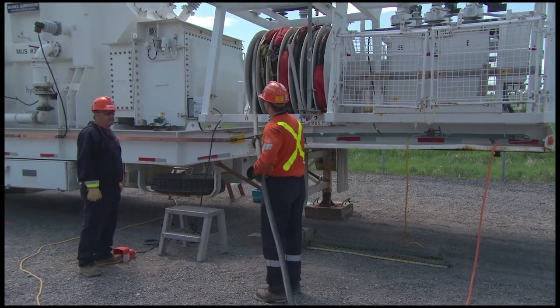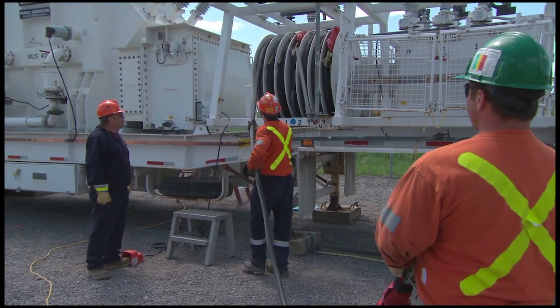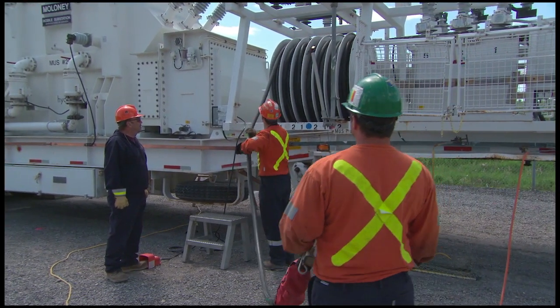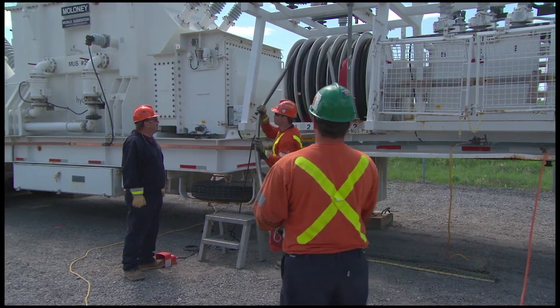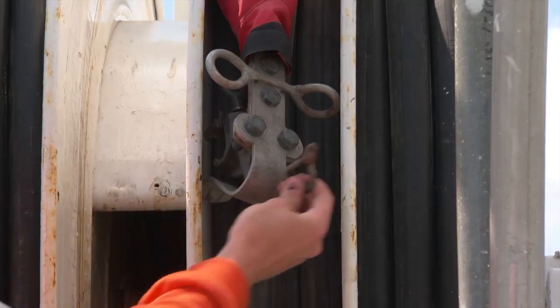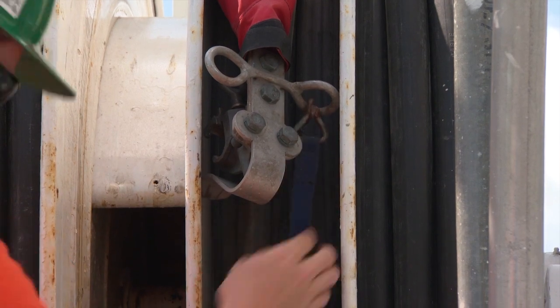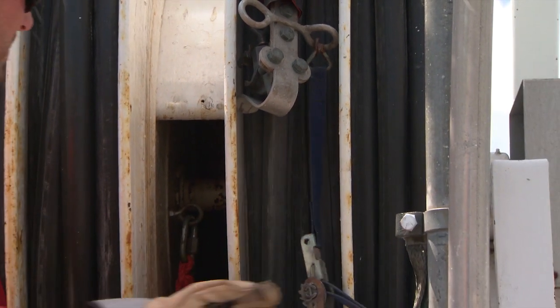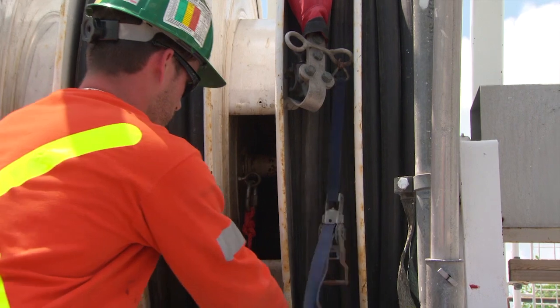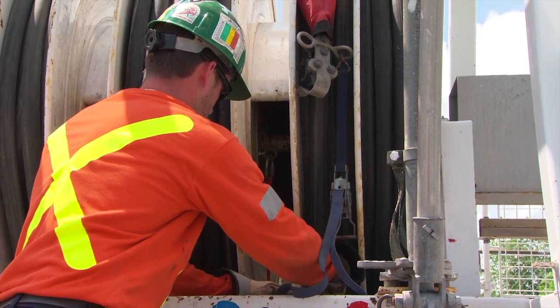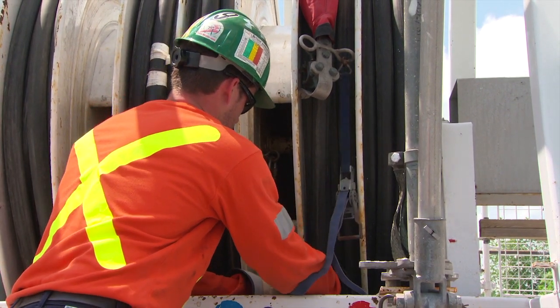Position the appropriate cable on the cable reel slot and fasten the tether lead onto the reel. Ensure the cable reel is rotating in the proper direction. Then gently lay the cable on the cable reel layer by layer. Once the bus end of the low-voltage cable reaches the reel, secure the free end of the cable to the reel using a ratchet strap or a piece of rope.